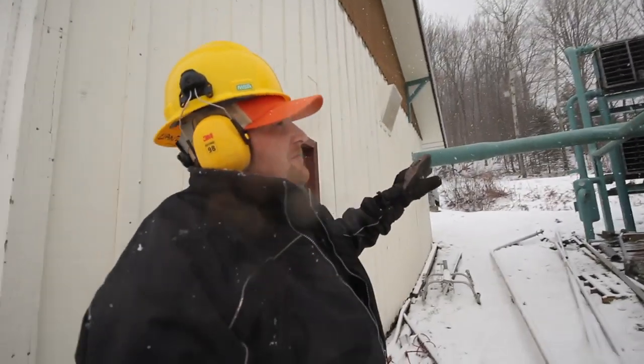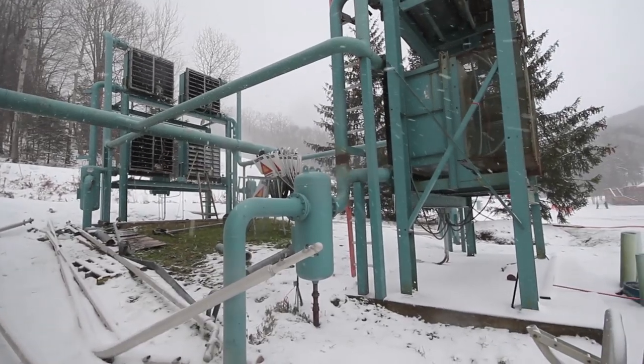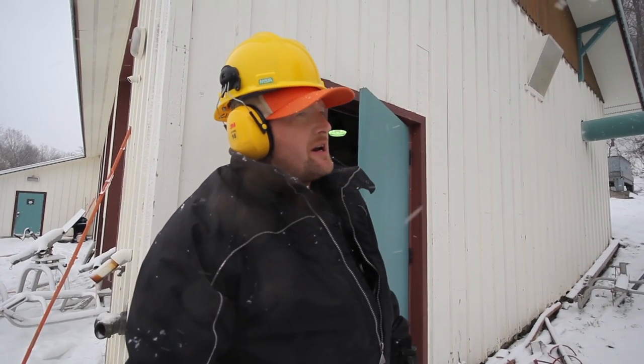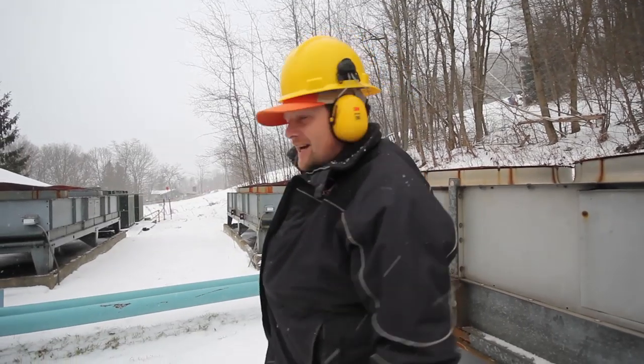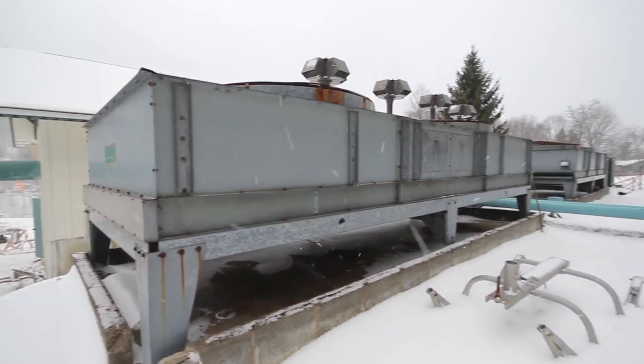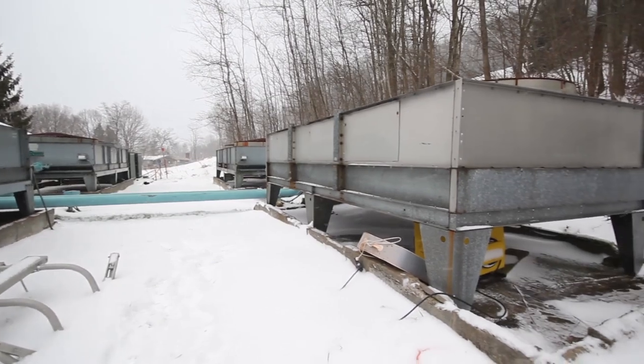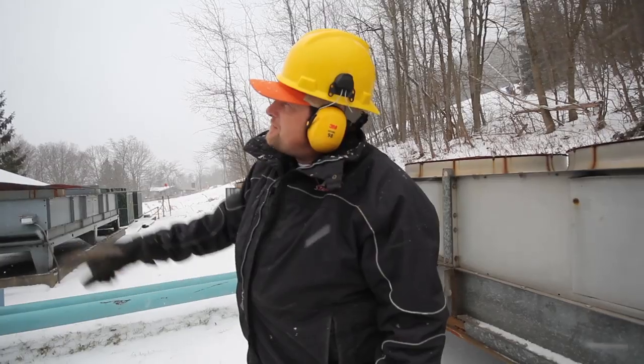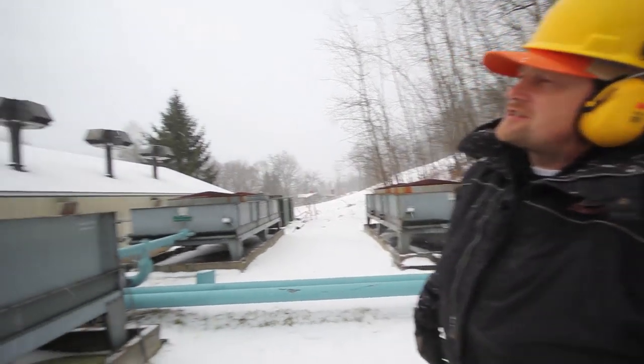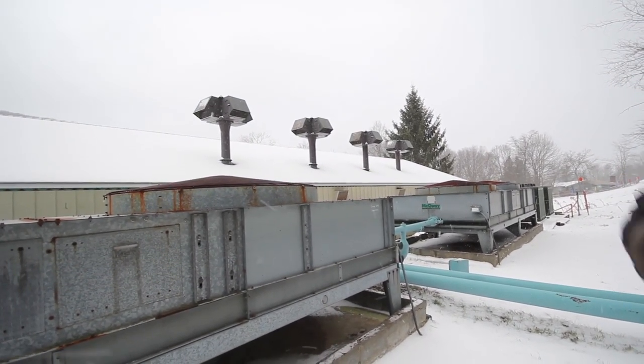This is the after air cooler — this is what's cooling the air leaving the building at 180 degrees, bringing it down to 45 degrees when it leaves these big fans. All these banks of fans you see are what is cooling the air compressors internally — they're big fans blowing down through big radiators. These big things up on the roof are where air is actually being sucked into the air compressor.